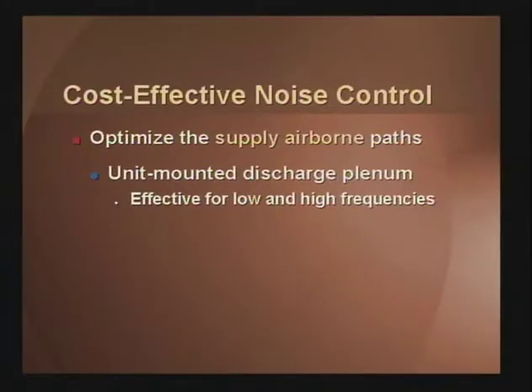Some of the other options you can look at relate to the supply airborne path. I get a lot of questions on duct silencers. When do I use them? Where do I use them? I'd like to submit to you there is another alternative, and that is a unit-mounted discharge plenum. Discharge plenums are effective on both low and high frequency, to some degree even better than many of the duct silencers. Plenums offer a low frequency reduction because of the end reflection that occurs in the plenum and the reduction of turbulence that occurs in the plenum. High frequency absorption comes from the fiberglass in the plenum.